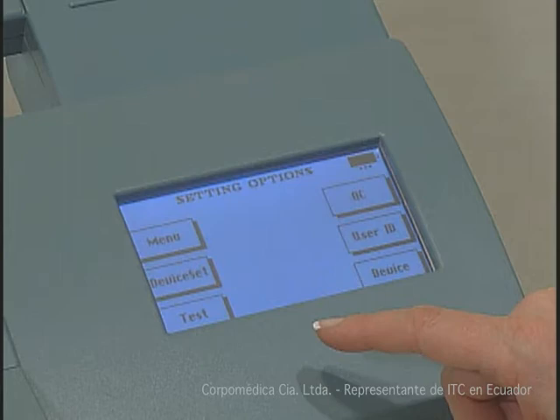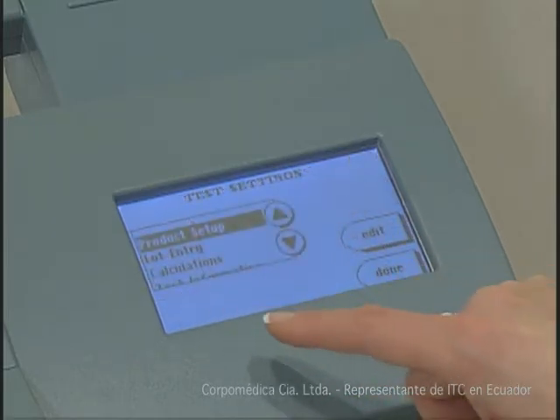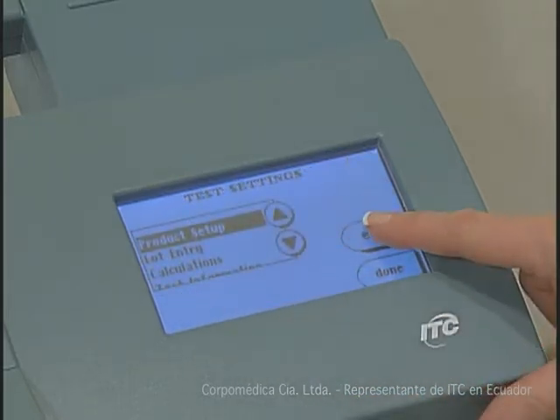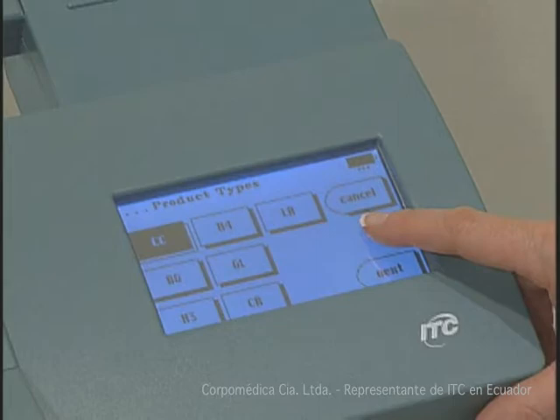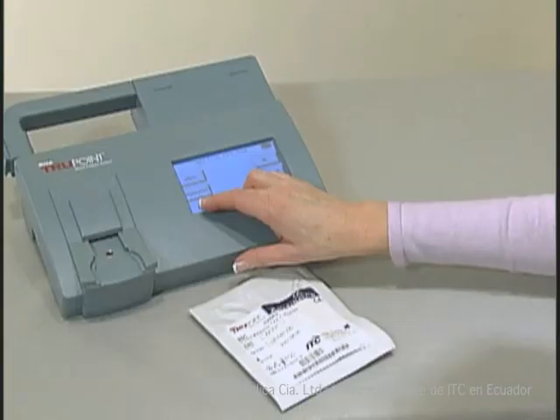To establish cartridge types, go to the Settings menu and press Test. Highlight the Product Setup button and press Edit. Then highlight all product types that will be used. Cartridge lots and calibration codes can be established either manually or automatically using the barcode scanner during the test sequence.